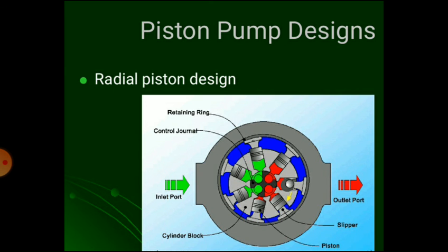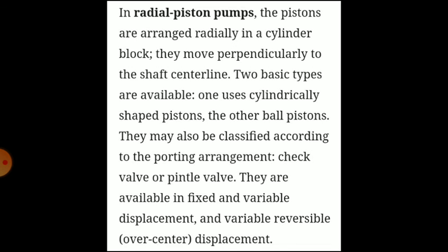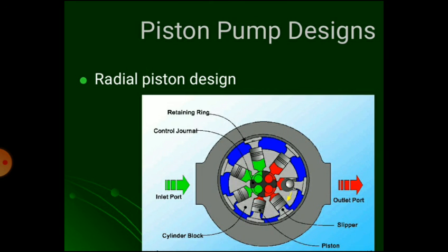Operation. As the piston block rotates in clockwise direction, the eccentricity causes the piston on the suction side to move inwards towards center due to spring force. The pistons on delivery side move outward due to reducing eccentricity.